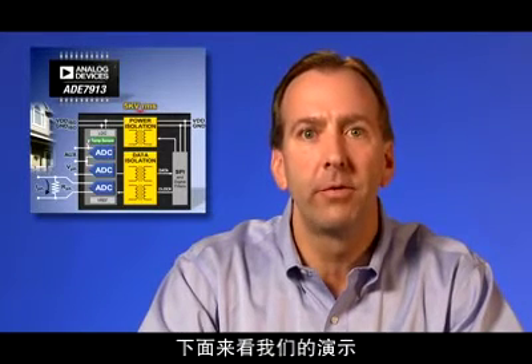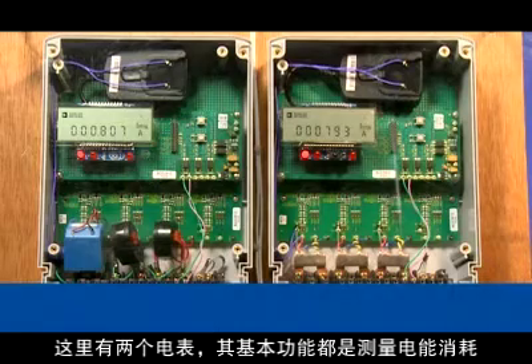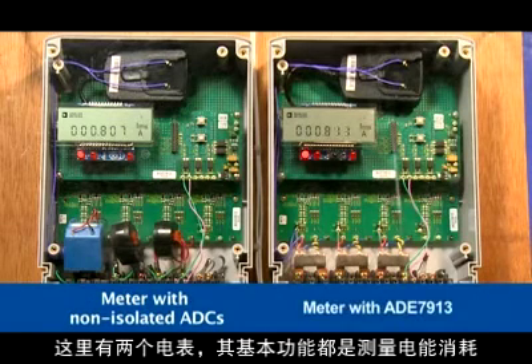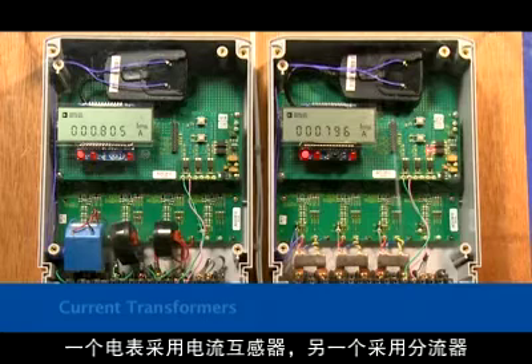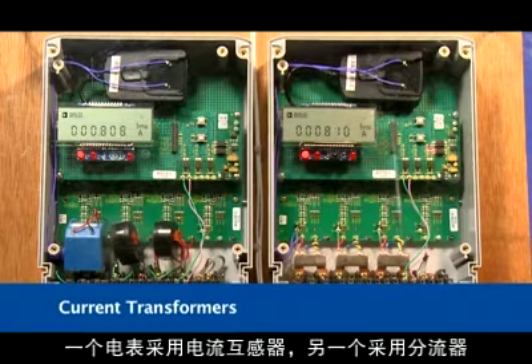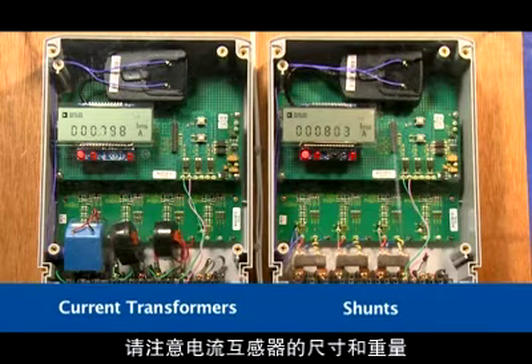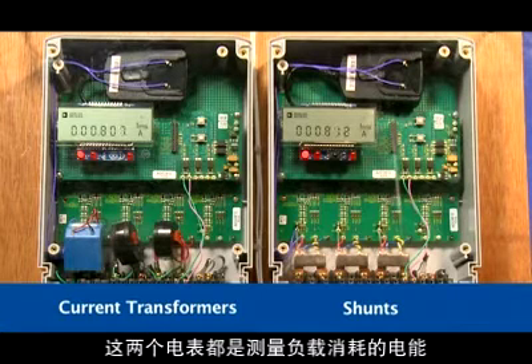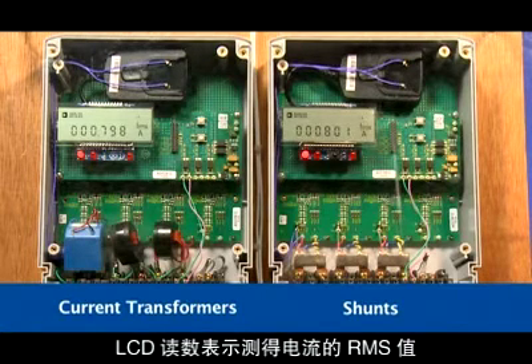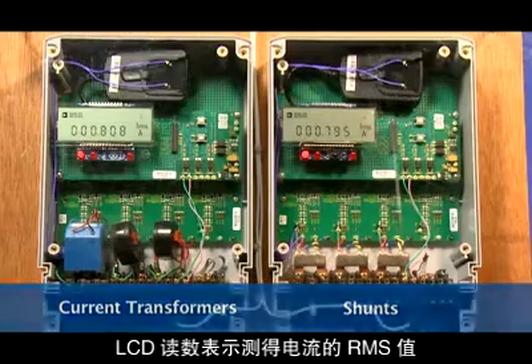So let's take a look at our demonstration that we've set up. Here are 2 meters that perform the same basic function of measuring energy consumption. One meter uses current transformers and the other uses shunts. Note how much larger and heavier the current transformers are. Both of these meters are measuring energy consumed by a load, and the LCD readout shows RMS of the measured current.